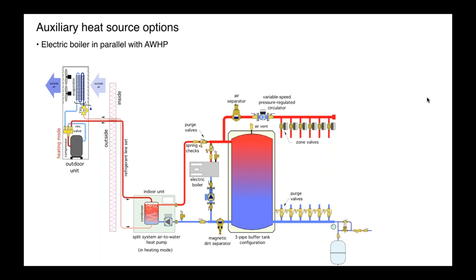Okay. Supplemental heat, we can use an electric boiler just in parallel with the heat pump. Make sure you have check valves so you don't get reverse flow, and purging valves. Okay. You could use a two-stage control where the heat pump is the lead stage and then the auxiliary boiler, the electric boiler, tops it off when necessary. And of course, you could size that electric boiler to do a full design load.